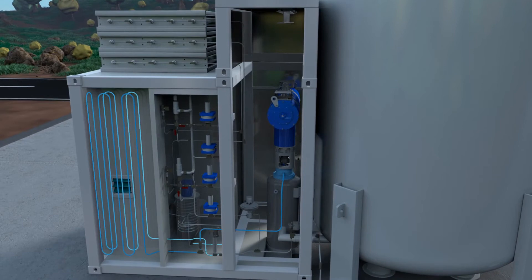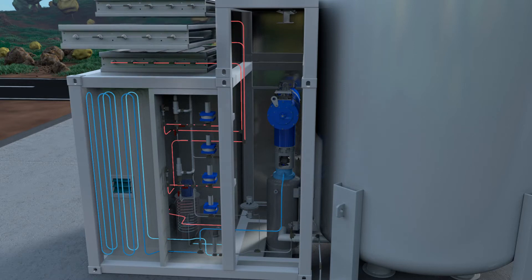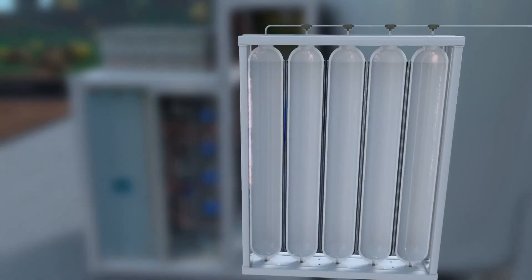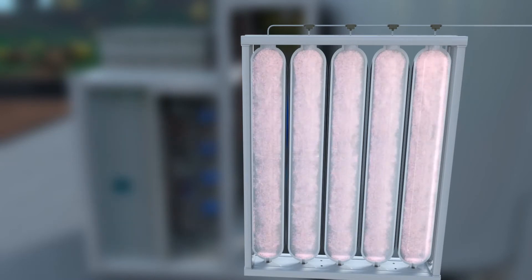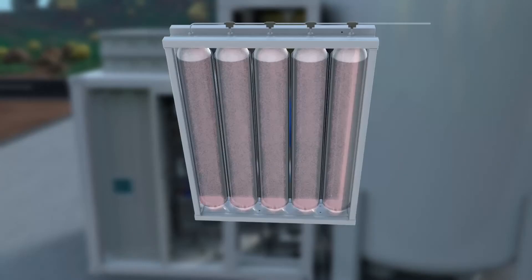The compressed hydrogen is filled into the storage tanks where the gaseous hydrogen is temporarily stored at a pressure of 1000 bar. The combination of the cryo pump and the storage tanks enables fast fueling even of several vehicles in a row.